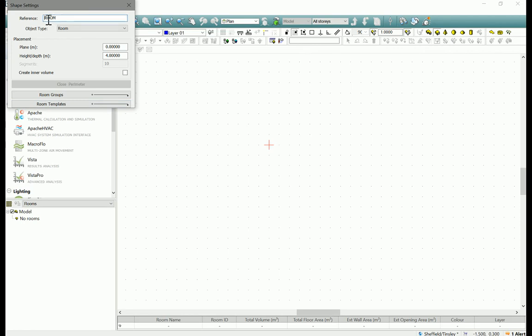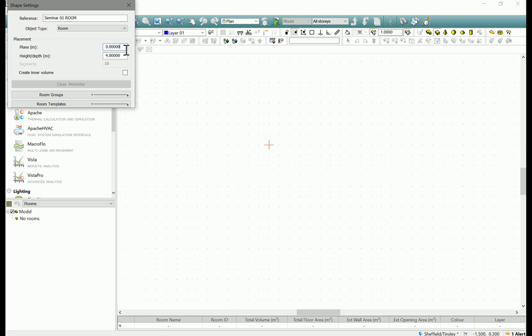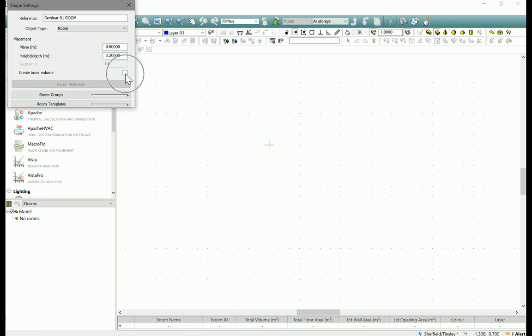Back into IES. So let's use the draw prism and reference. We can give this a room name so let's call this seminar one. Object type, at the moment we're only concerned with rooms. We'll look at the other ones in another video so leave that on room. The plane, so what height are you modeling the floor of your zone? We'll just leave that at zero for now but obviously if you were modeling at a different level you would change that. And the height of that zone, so really think of this as the ceiling level, the ceiling height. So I'm going to call that 3.2.